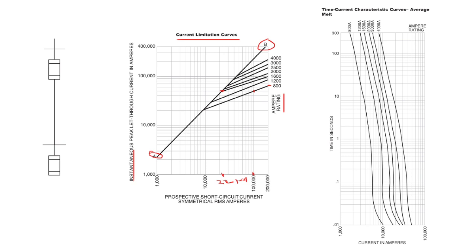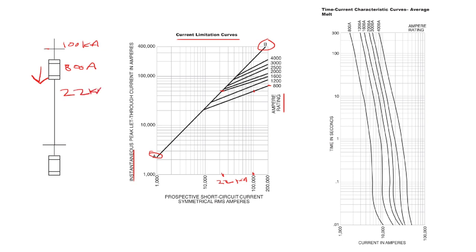If we look at our one-line diagram, we can see that up here we have 100,000 amps of fault current on this bus, and then we have an 800 amp fuse that will only let through about 22,000 amps of symmetrical fault current. So down here on this bus, we only have to be concerned with 22,000 fault current amps because of the current limiting 800 amp fuse above it in the system.